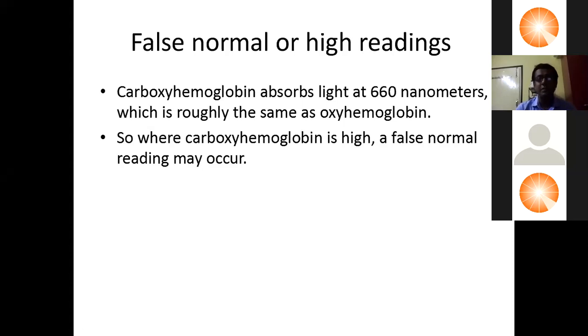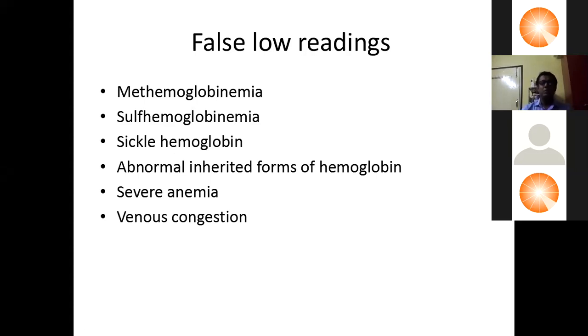There are some conditions where we can get a false normal or false high reading, like carboxyhemoglobin, that is CO poisoning, because carboxyhemoglobin absorbs light at 660 nanometer, that is red light, similar to oxyhemoglobin. So it mimics oxyhemoglobin and gives a false high SpO2 in case of carbon monoxide poisoning. Now, there are some conditions where we record a false low reading, like methemoglobinemia, sulfhemoglobin, and sickle cell hemoglobin. Methemoglobin and sulfhemoglobin absorb both red light and infrared light, in different amounts, and they also affect the reading. So we get an inaccurate low reading.